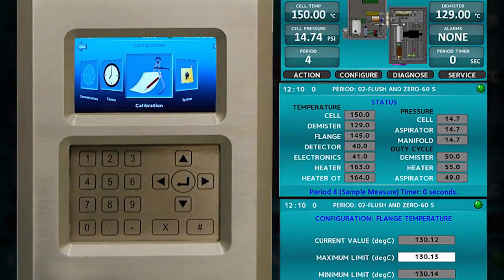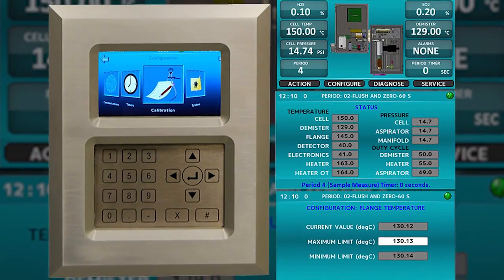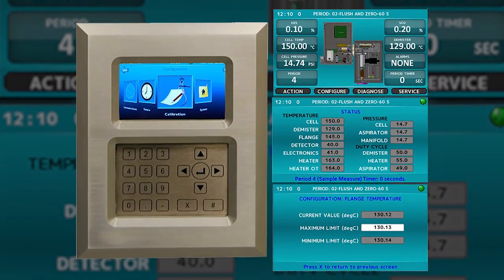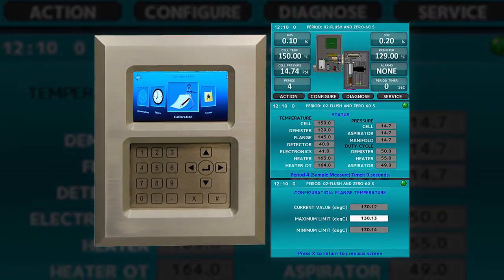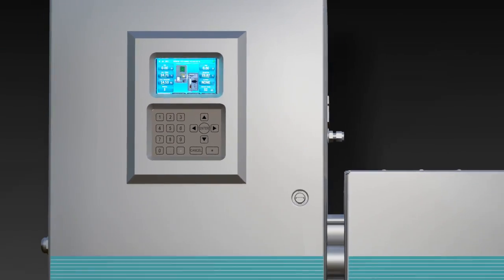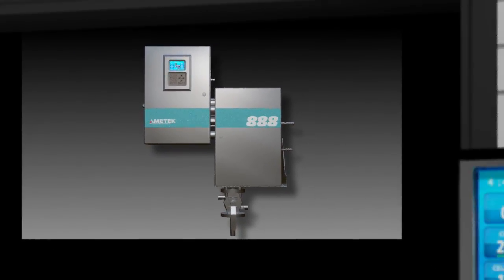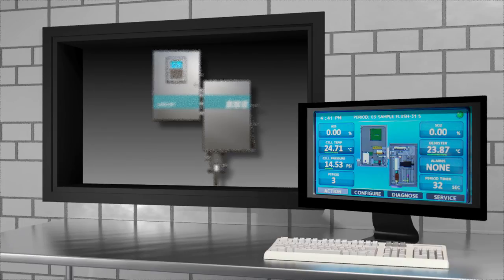The use of three intelligent diagnostic models identify potential problems and take corrective actions before they would otherwise lead to unscheduled downtime. The results are then transmitted to the distributive control system via built-in ethernet and modbus digital connections.